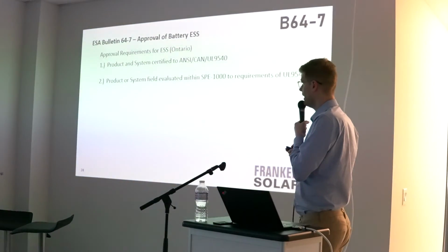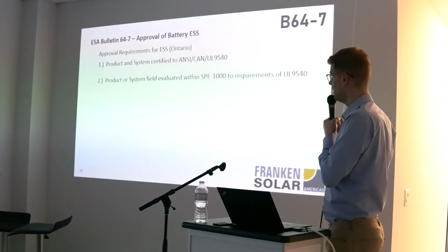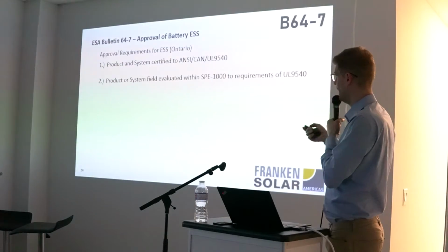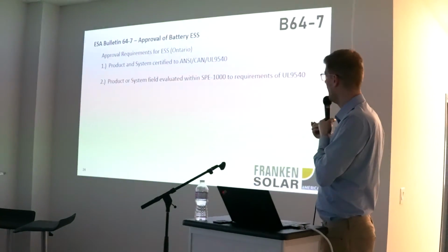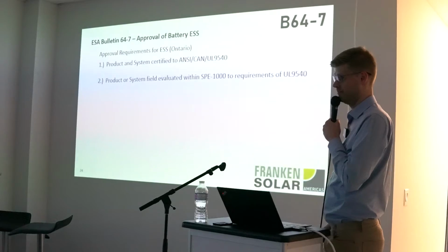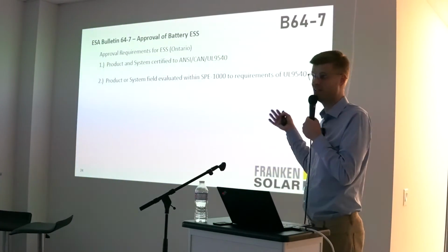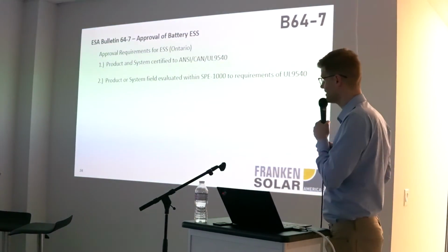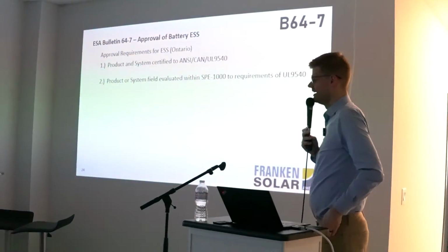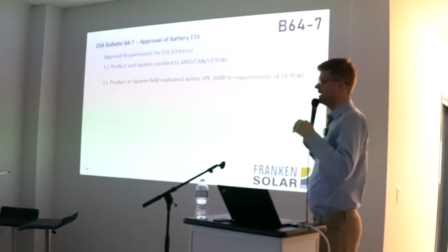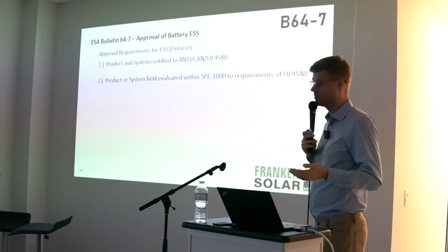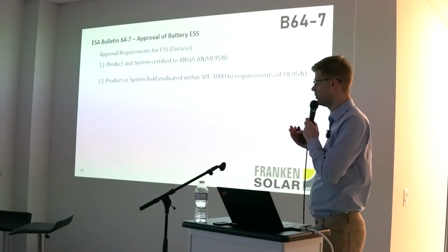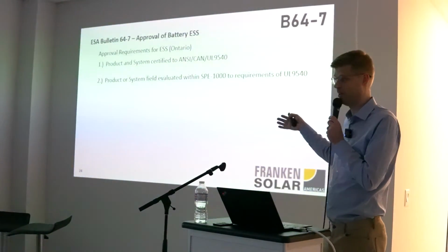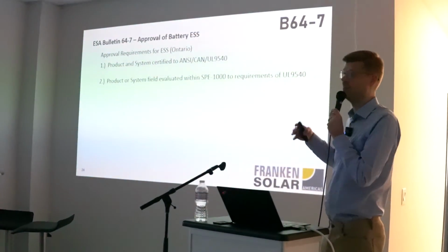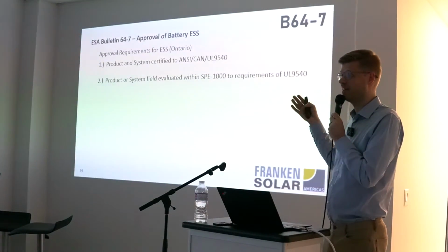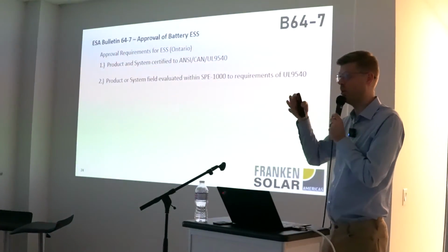So you can do a product or field evaluation under the SPE 1000 to the requirements of 9540. That sounds easy, but it's not as easy as it might be listed on that bulletin. The problem is that it's relatively expensive, and a lot of time goes in. You have to do a lot of communication with your testing lab that comes out and does the SPE 1000, and they charge you quite a bit of money for getting your system certified with the components you select.